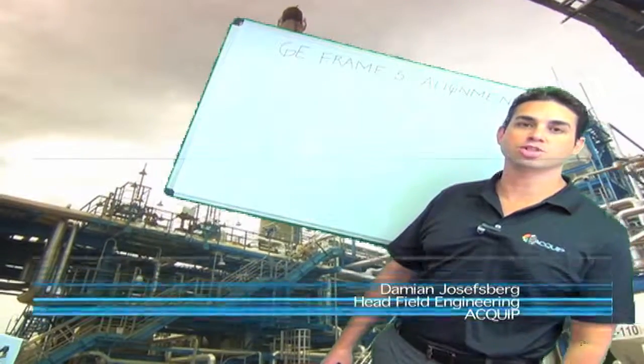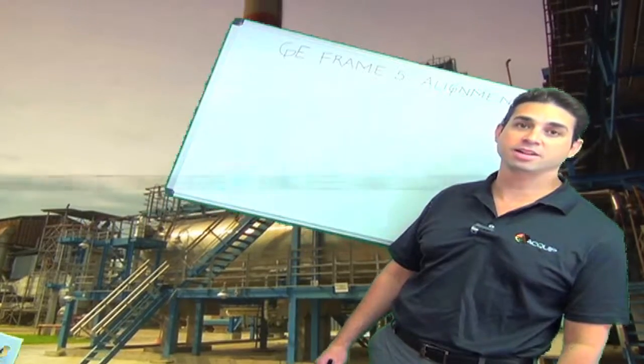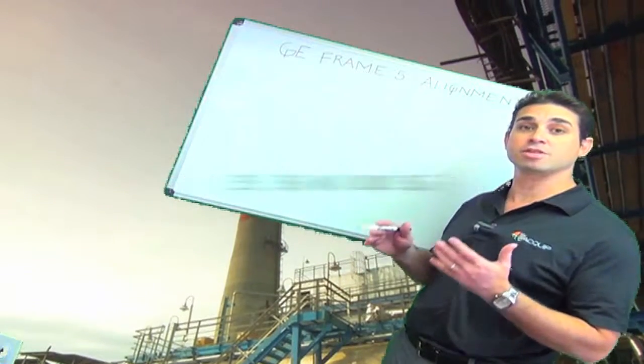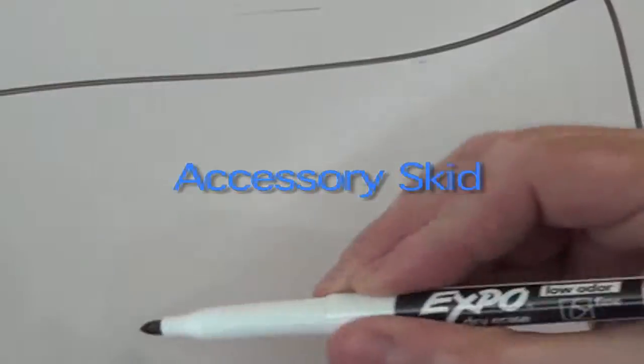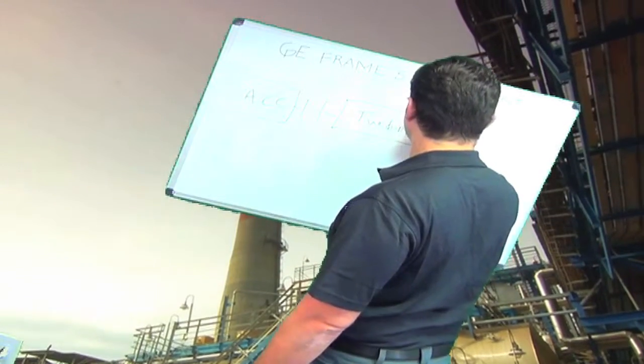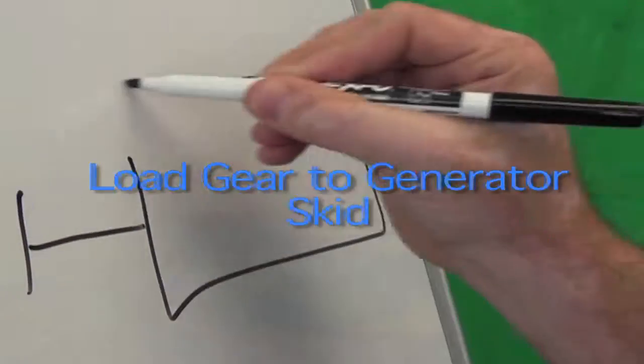Hi, I'm Damian Josephsberg from ACQUIP, and this is GE Frame 5 Alignment. A gas turbine alignment is actually a machine train alignment because you're lining up three different skids. On a Frame 5, you have your accessory skid coupled to your turbine skid, and that's coupled to your load gear generator skid.